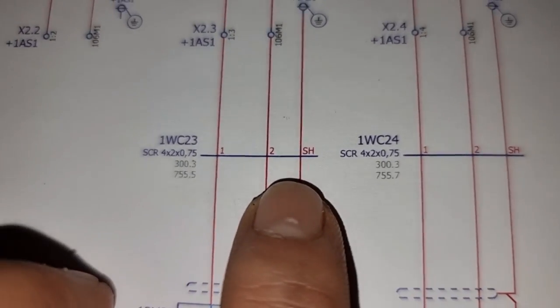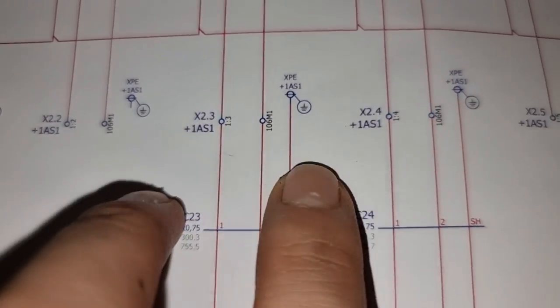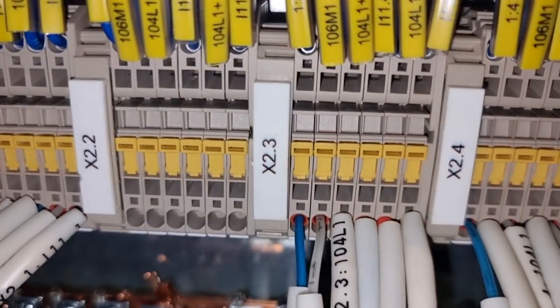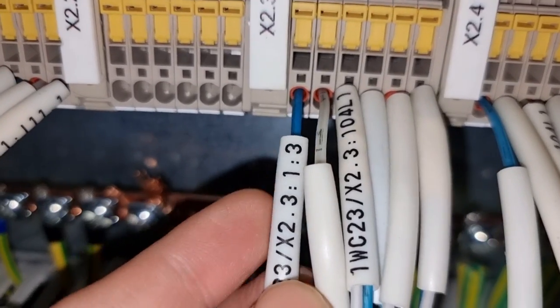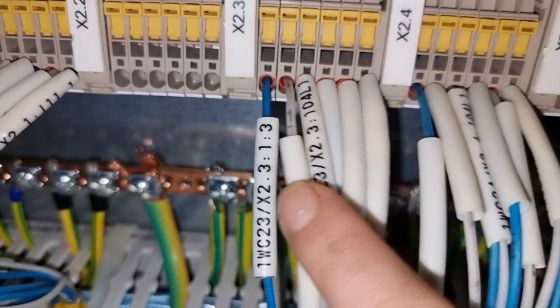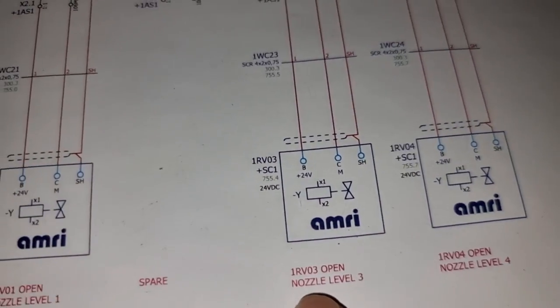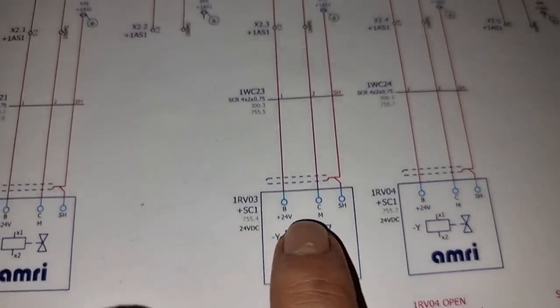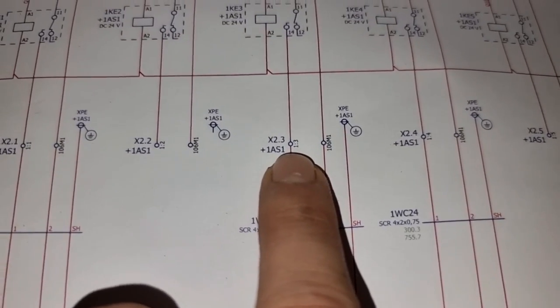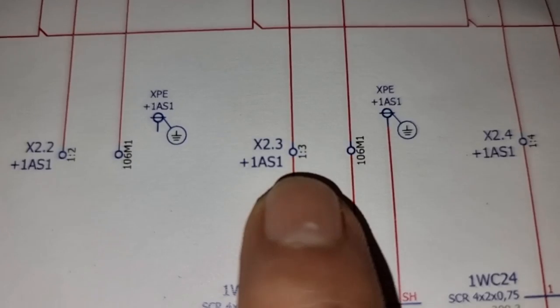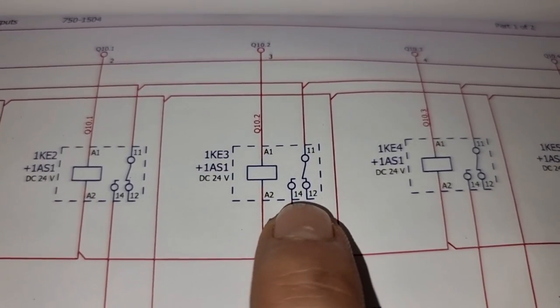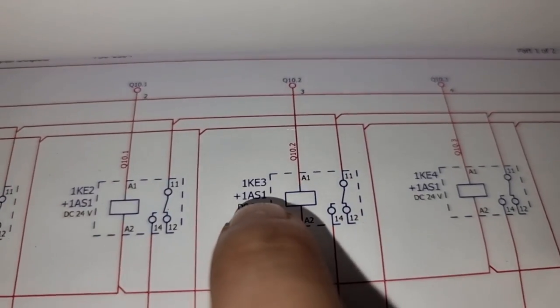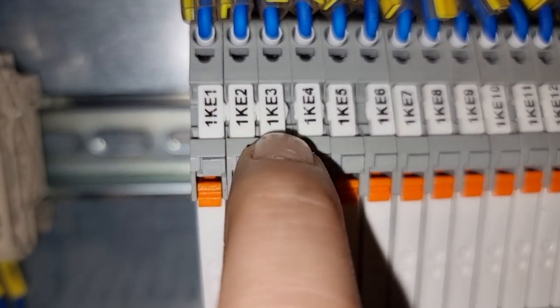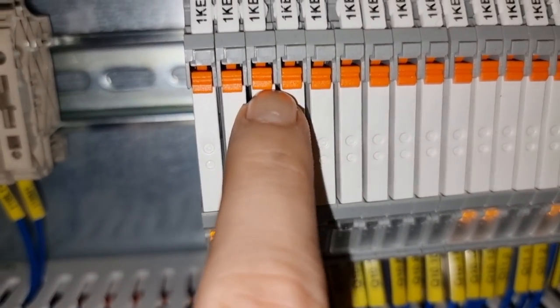Then moving forward, there is this solenoid valve which will open once there is 24 volts supplied to it, and this is connected to the terminal X2.3, and these are the cables connected to our solenoid. To check, this 1RV03 will open once you have the supplied 24 volts. So checking our cable, these are going to a group of relays, which specifically for this valve is this 1KE3. From this terminal block, this goes to this 1KE3, and this is the relay.